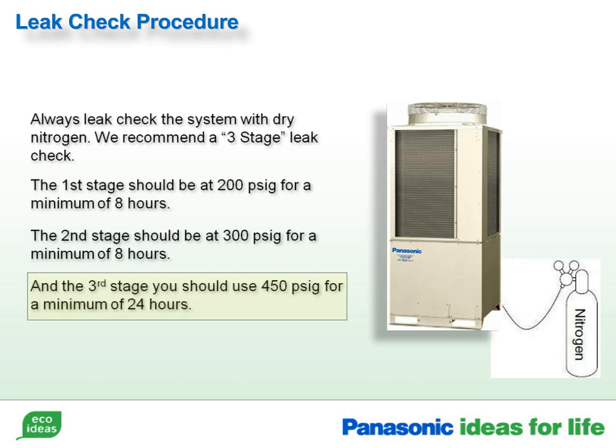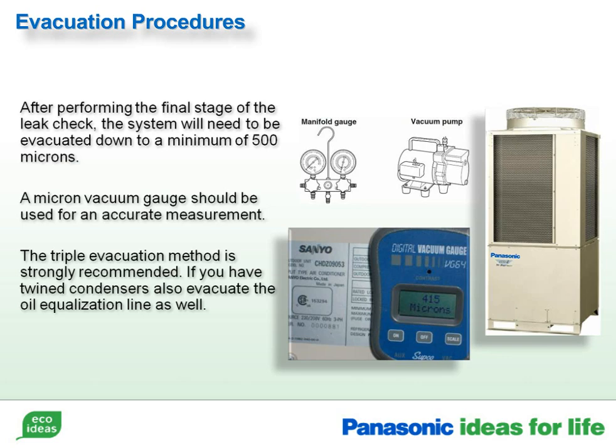24 hours. This portion of an ECOi installation is the most critical. If you do not perform a thorough leak check at this time, it can become costly and very time-consuming to find a leak later on. Once you are sure that you do not have any leaks in the refrigerant lines, the system will need to be evacuated down to a minimum of 500 microns. A micron vacuum gauge should be used to ensure that you have an accurate measurement.